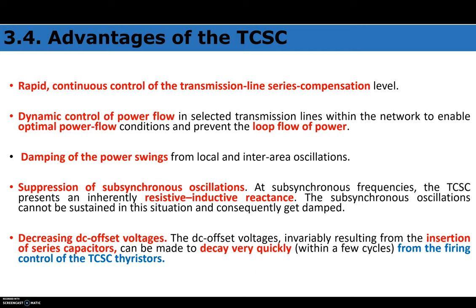Now, what are the advantages of a thyristor control series capacitor? Since it is controlled by thyristor, it gives rapid and continuous control. The continuous control is achieved because a thyristor controlled reactor (TCR) is connected in parallel with the series capacitor. A fixed capacitor alone allows no variation, but the TCSC — a combination of a fixed series capacitor with a parallel thyristor controlled reactor — provides continuous control of transmission line series compensation.